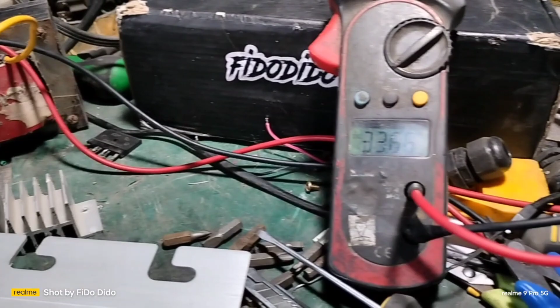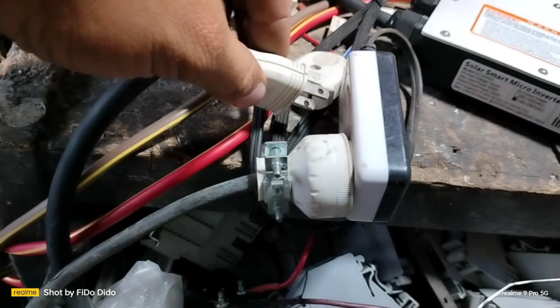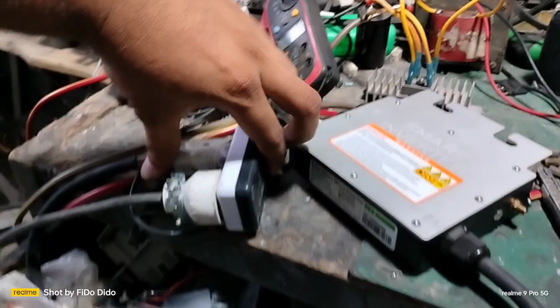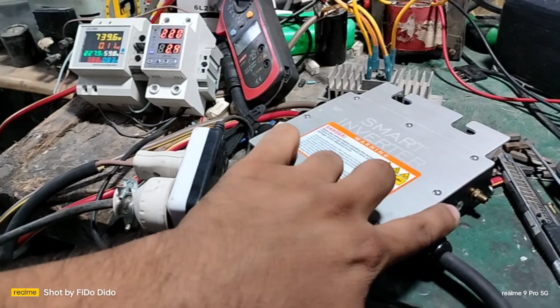740 watts. As you can see, the inverter is not yet activated. Its idling is 33 volts. Now I'll turn on the inverter by connecting it to the grid, parallel with the load. We're all on the output of this one. Connecting the inverter. Now it's blinking, and as you can see the power output is still 700. I'll wait for it to turn green. Let's wait, now it's green, and it should be dropping.